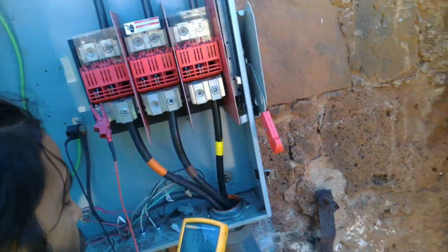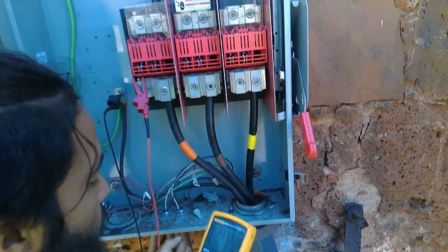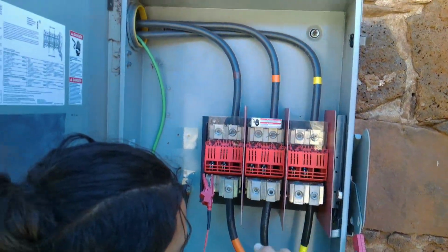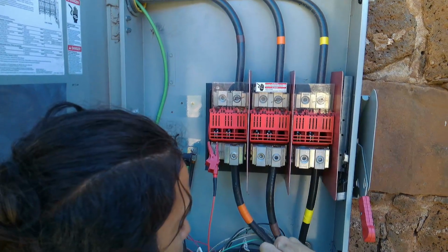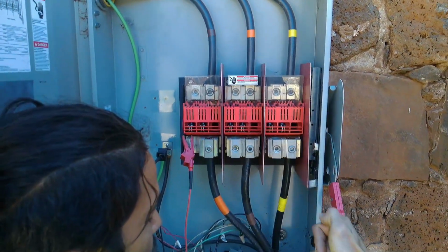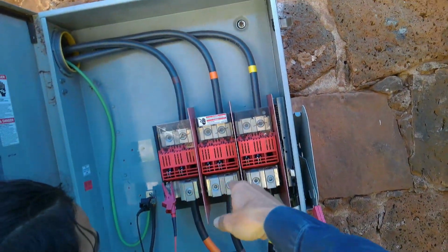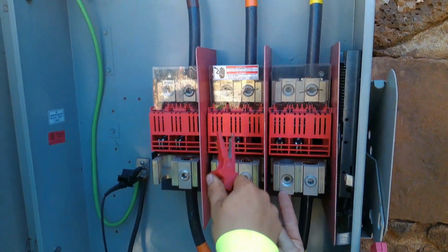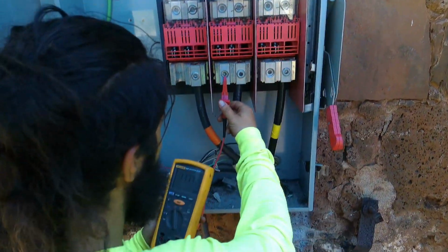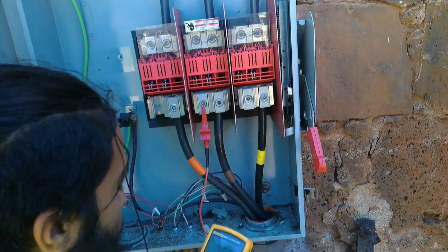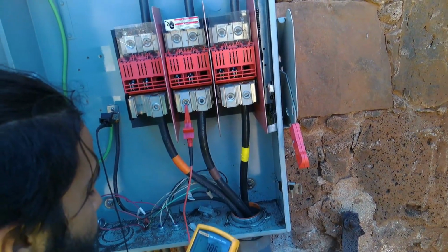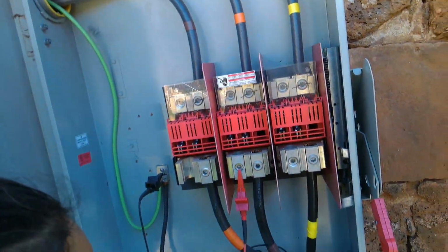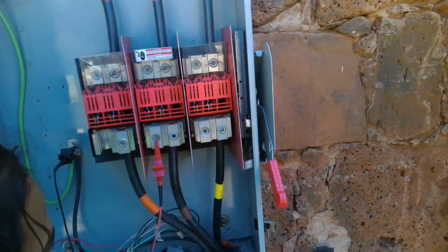We'll say greater than 1.5 gigohm. 1.7, 1,777,000,000 ohms. So do that on line 2 now. And maybe you gotta come like this, you know. Yeah, there you go. Go ahead. It should be the same thing, because the other end of this wire is this wire is this wire. They're all connected. Good.